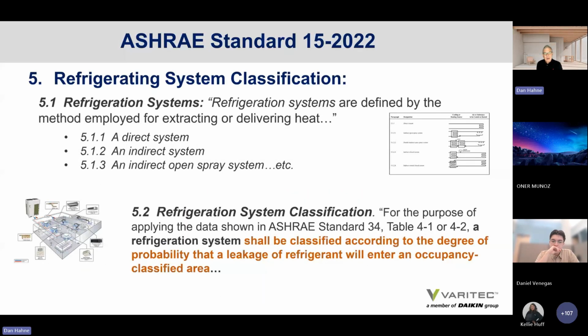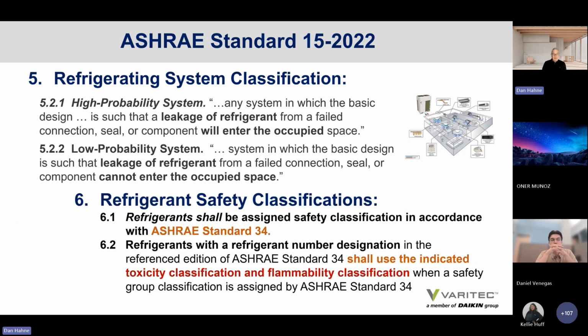Section 5.1, refrigeration systems are actually defined. I only listed 3 here. I think there are about 6 or 7 in order to assign how that system might impact the design of a refrigerant system serving occupied spaces. And then there is section 5.2, which is a refrigeration system classification for the purpose of applying the data shown in ASHRAE 34, table 4-1 or 4-2, that classifies according to the degree of probability that a leakage of refrigerant will enter an occupancy classified area.